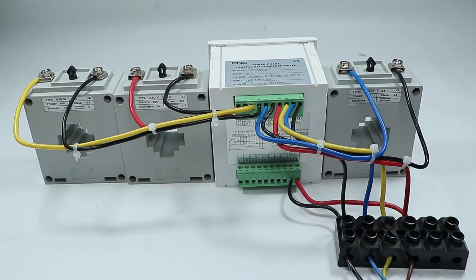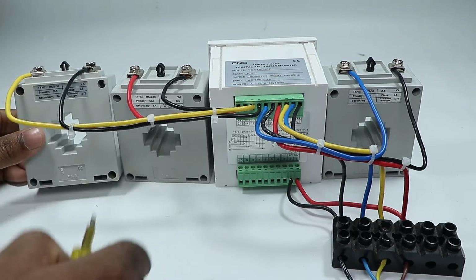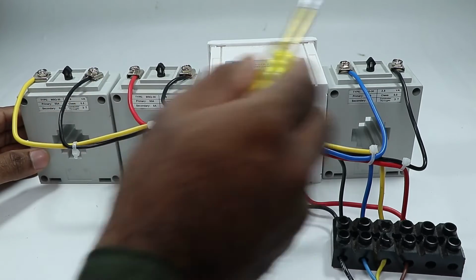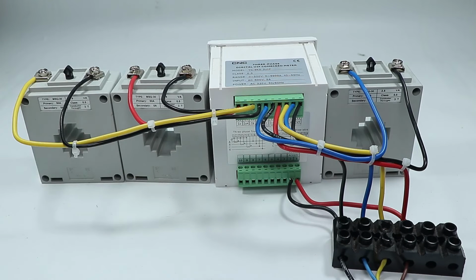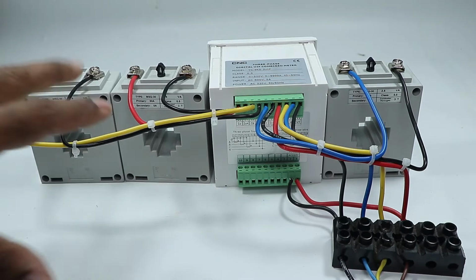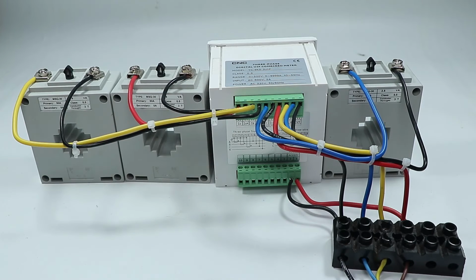After this much connection, you have to connect one more wire. In all these CTs, at the S2 terminal, you have to short all these terminals together. After shorting them, connect these with earthing. Let me show you the connection directly.